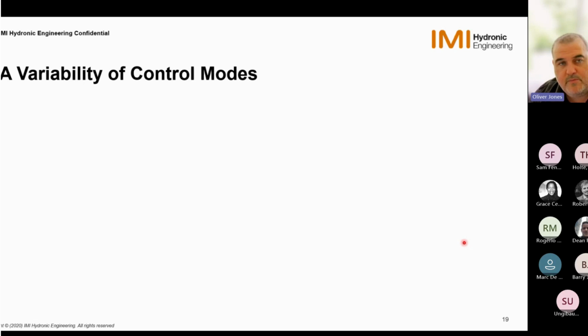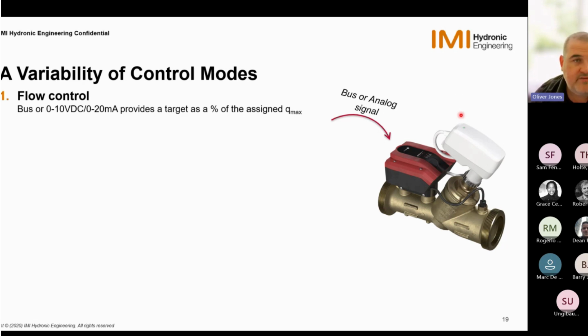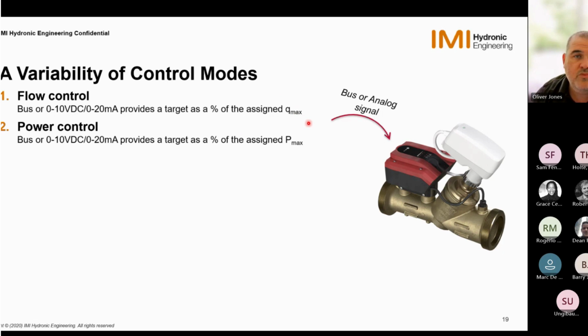So just to touch on the variability of control modes in brief, we have seen all of these anyway. So our flow control, which is either over bus, so Modbus or BACnet, or via 0 to 10 volts or 0 to 20 milliamp. So this is our signal into the valve to be able to provide a target as a percentage of our assigned Qmax. So that's our maximum flow. Power control, which again is over bus or our analog signals, and this provides us a percentage of the assigned Pmax, so the max power.